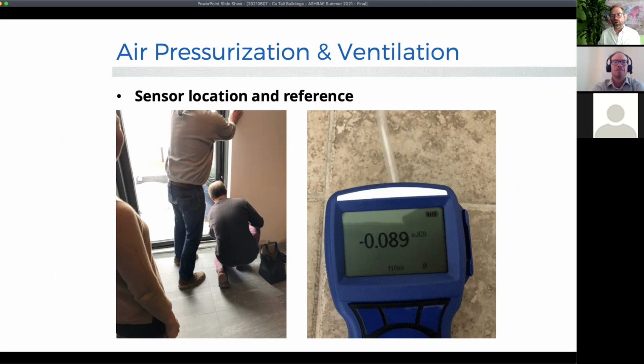On this building, sensor location and reference point were very important. The design engineer had designed it for pressure control, but what we really wanted was volume of air control—understanding how much volume is coming into the building and how much is going out, and controlling it based on that.